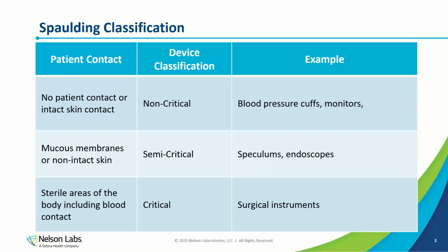Now, I know these procedures are not intended to see a lot of blood or other contamination, but I would still, in this case, just due to where the robotic arm is being used in reference to the patient, as well as the nature of the procedure that's happening, recommend an intermediate level disinfection. But that is an excellent question, because that is a tricky part with these devices, as you have the robotic part with the end effector that is patient contacting, and then you have the arm higher up above that's going to be draped that is not patient contacting. So excellent question.